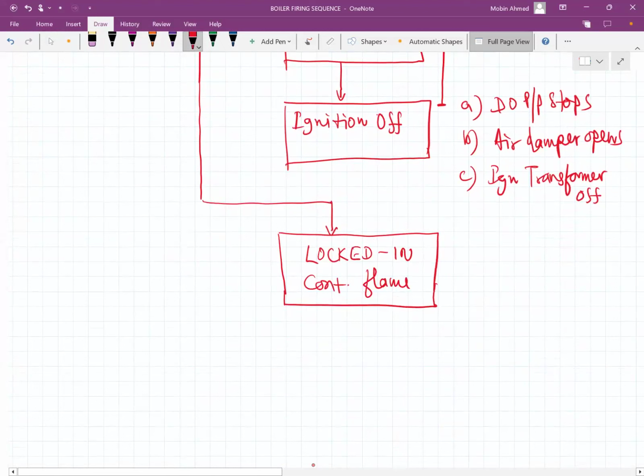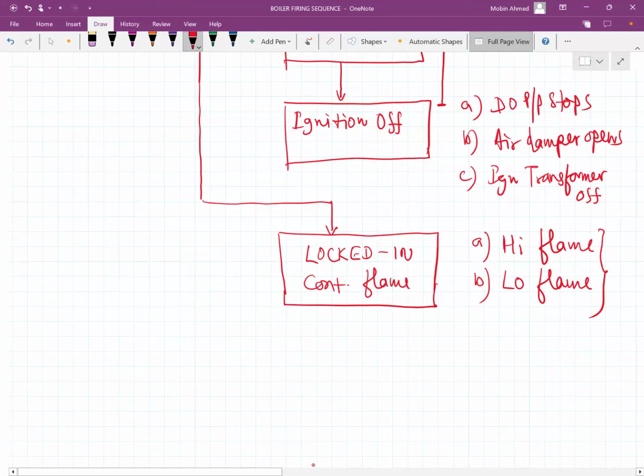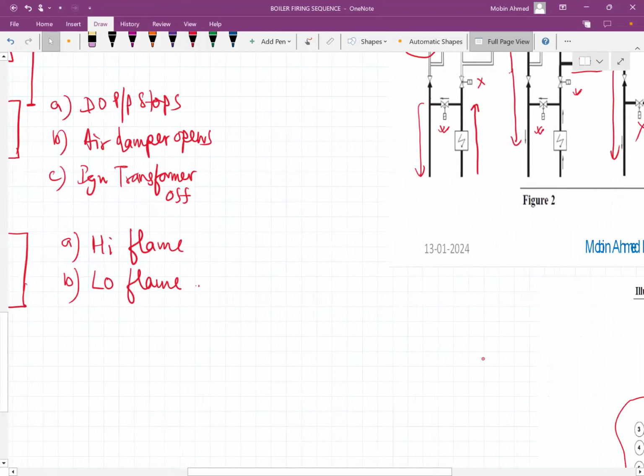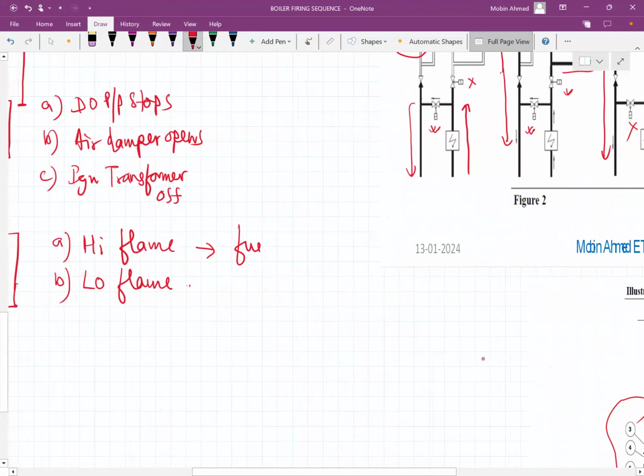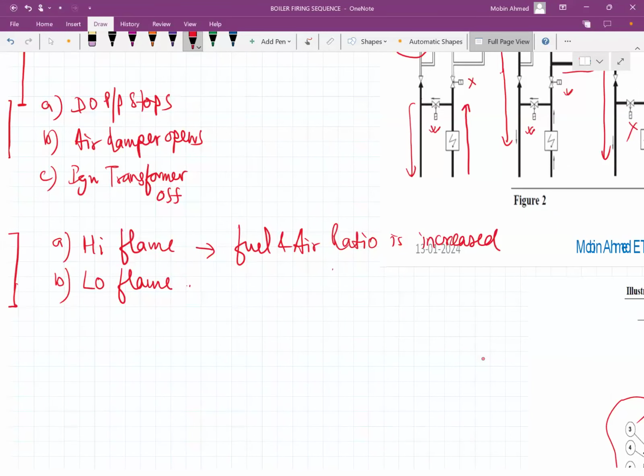And in locked-in, two things are going to happen: the high flame and the low flame. I hope if you have heard about this, you will know the high flame and low flame. So it will be regulated for the high flame. If you have a servo motor, it is very easy, and if we have a solenoid, then also it will be the same. High flame means the fuel and air ratio is increased. Generally, this happens during the starting.